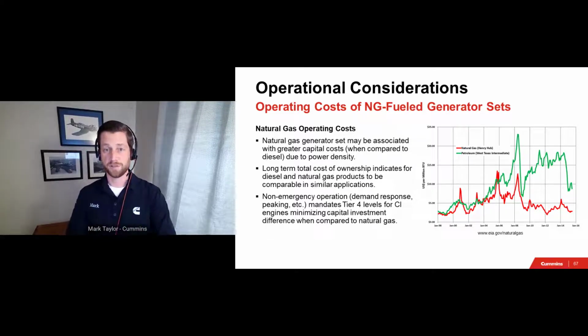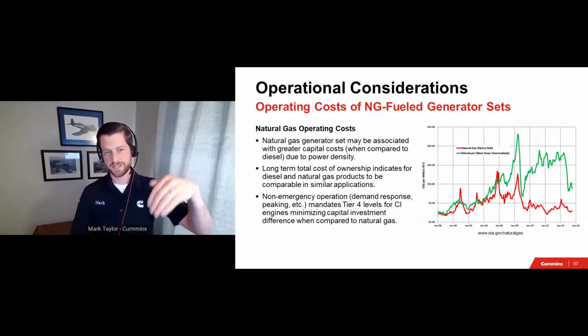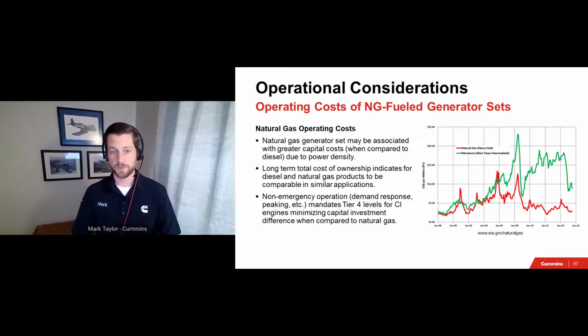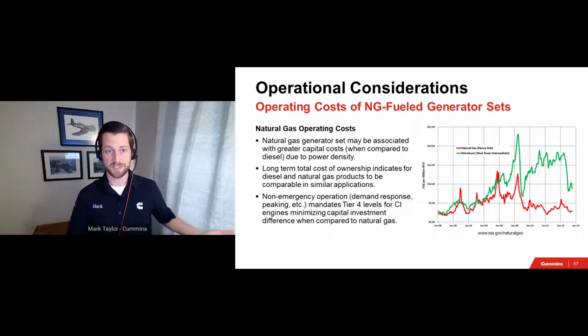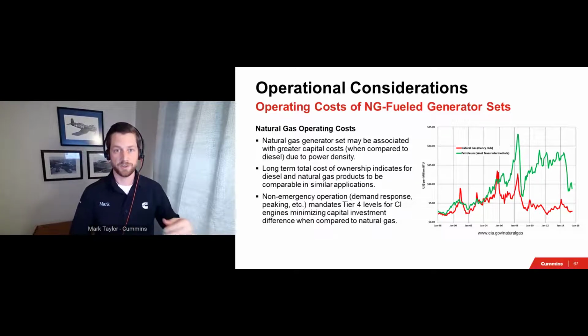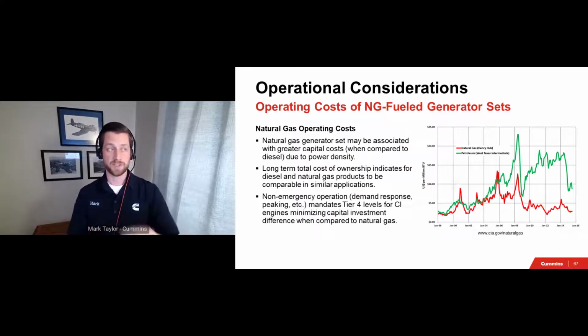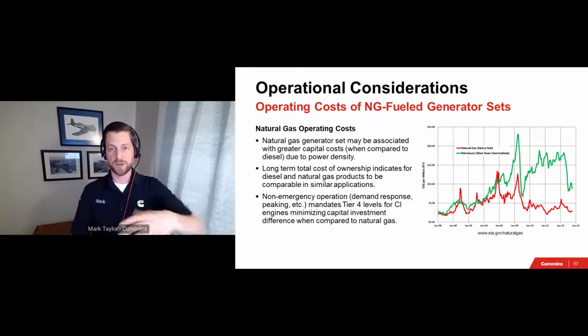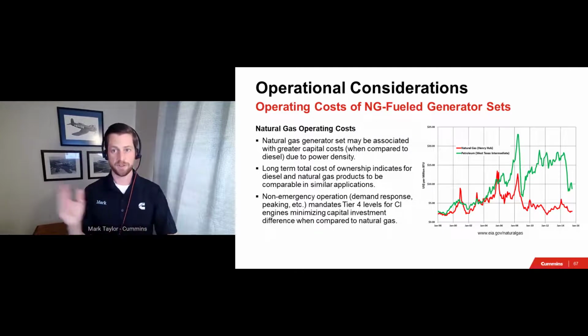Over the long term, however, due to increased costs of procuring and maintaining diesel fuel, that edge does tend to erode. That is one reason why, when it comes to the non-emergency space for demand response or peaking or continuous duty, it's gaseous fuels that are so often used. They're quite popular for that purpose. So if you're working with a customer that is open-minded to the possibility of both diesel and gaseous fueled generator sets for their next project, present the value proposition in terms of near-term versus long-term costs, as well as the convenience of not having to maintain diesel.